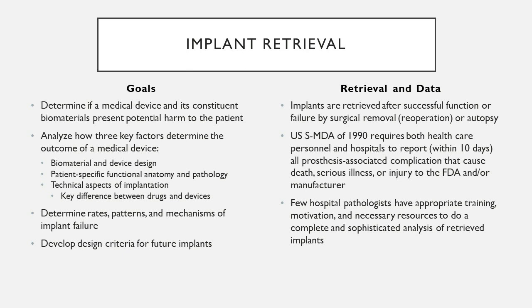This has much to do with the interaction with a particular end user as opposed to the material device design itself. Now, during a retrieval process, there's a few things that engineers want to analyze to determine the outcome, or what factored into the outcome of a medical device. The first is the biomaterial and device design itself. The second is patient-specific functional anatomies and pathology, in a sense, their response to that particular device and how that affected the device itself. And then lastly, the technical aspects of implantation.